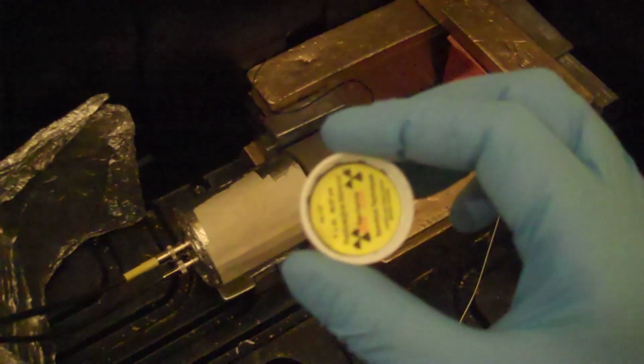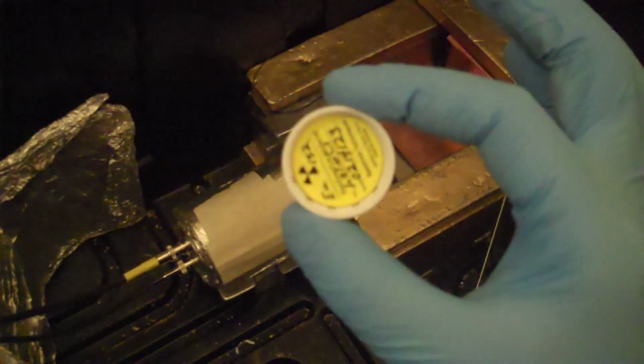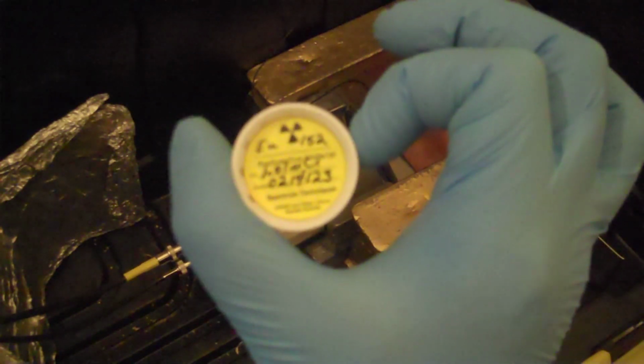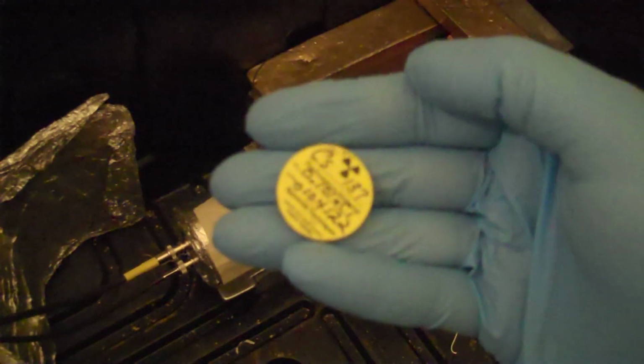Works great though. This is a cesium-137 source I use of 37 kilobecquerels for calibration. And microcuries, that's 1 microcurie. Whenever I'm trying to calibrate something and I need to know the exact amount of gammas that I'm getting, I use these calibrated sources. They have a 95% accuracy for gamma. In this case, I have europium-152, 37 kilobecquerels, and I have cesium-137 at 3.7 kilobecquerels, 1/10. Look at that. Alright. Now, these are very small amounts of radioactivity, of course, but still, they're enough.